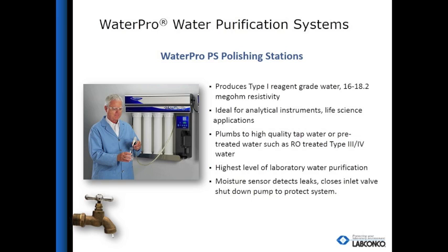The 4 systems are the WaterPro General Chemistry System for Type 1 water, the WaterPro HPLC system for ultra-low TOC levels, the WaterPro UF system for water free of endotoxins or pyrogens, and lastly the WaterPro HPLC UF hybrid system that delivers both low TOC and pyrogen-free water. This is great for laboratories with multiple lab divisions.